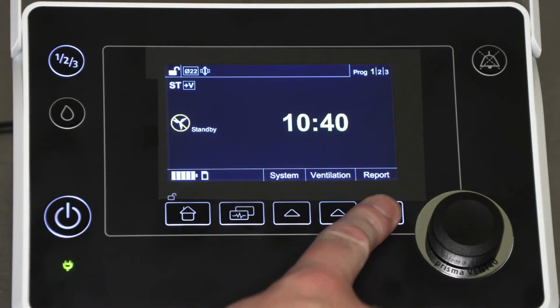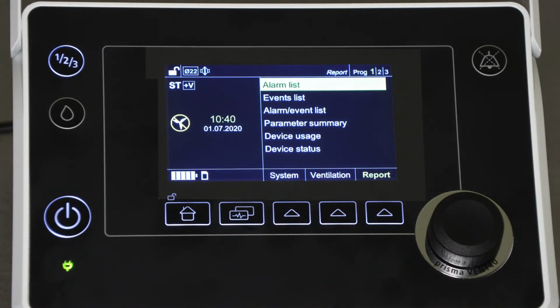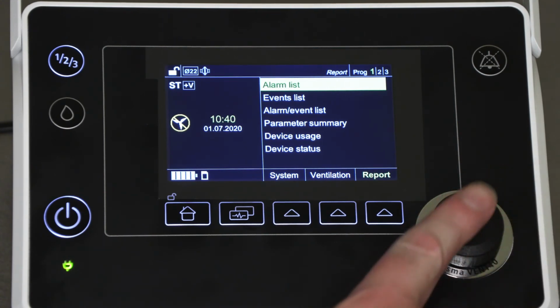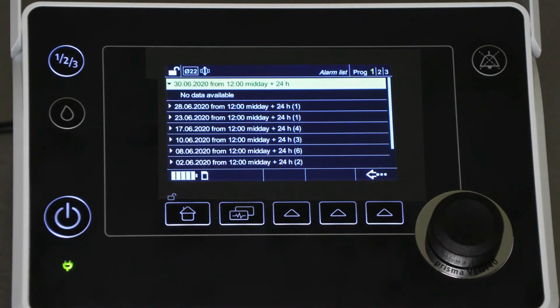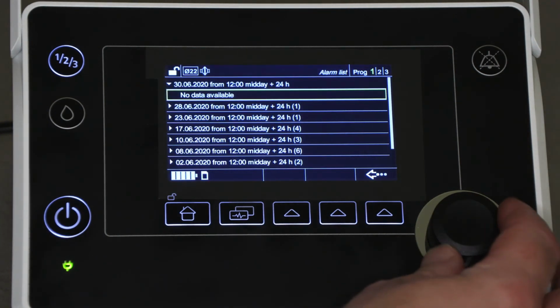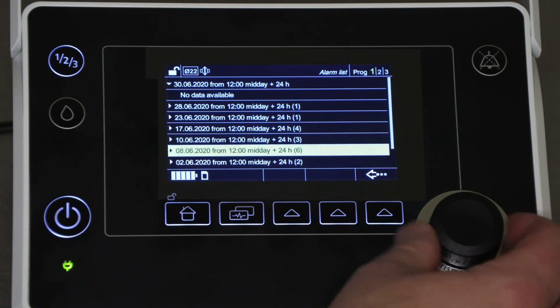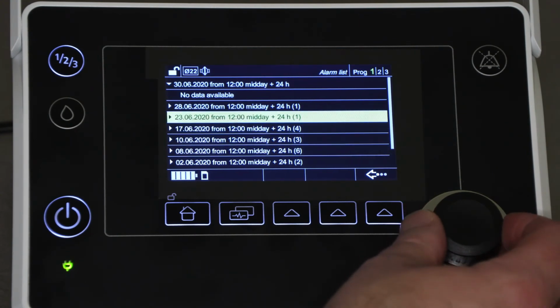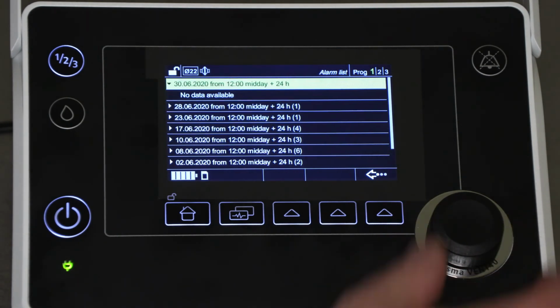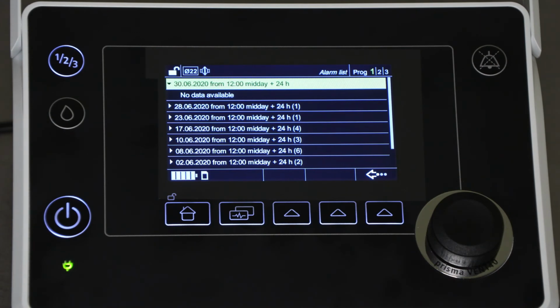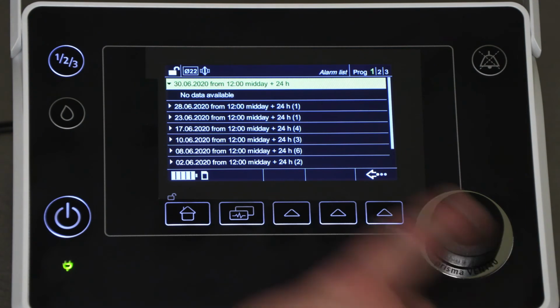When you enter the report menu by pressing the report button, you'll see another short list of items that can be viewed for information purposes. Firstly, there's an alarm list. This will show a list of any alarms that may have occurred recently, along with the date and time of the alarm. This is useful if it's reported that there was an alarm at some point, but the name of the alarm on the screen was never noted.